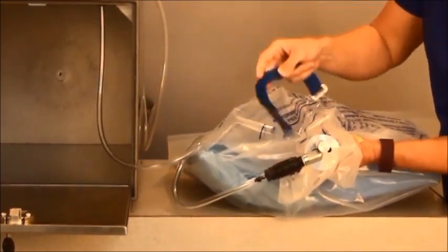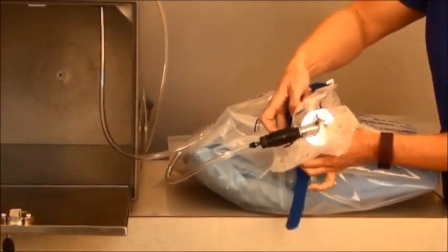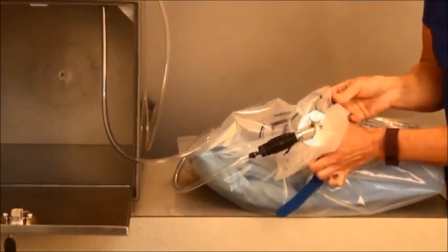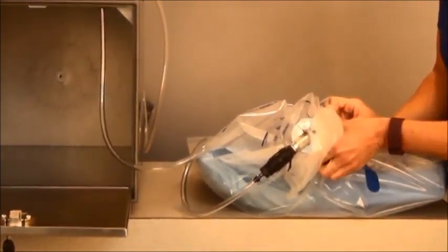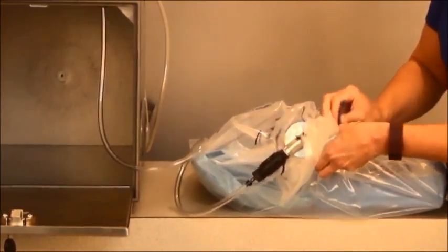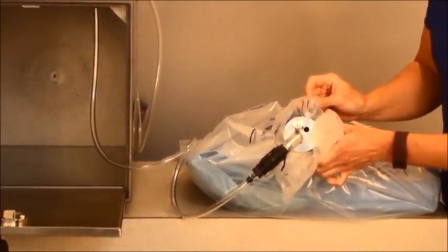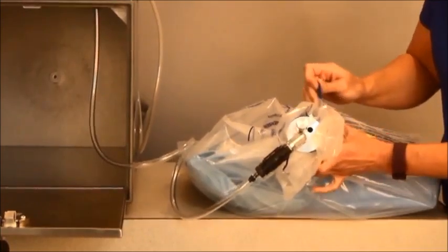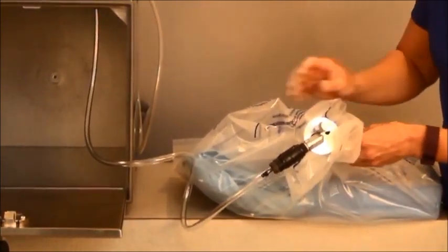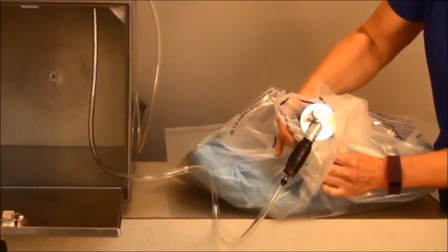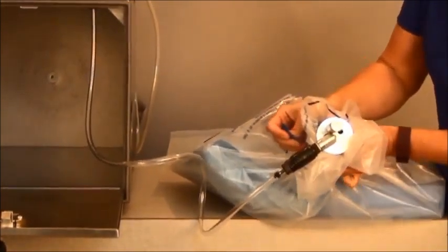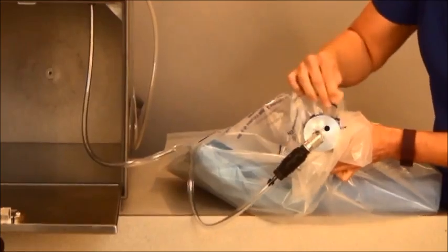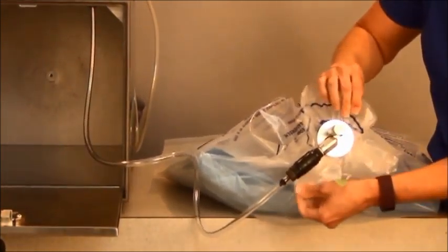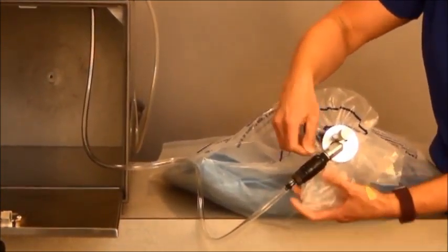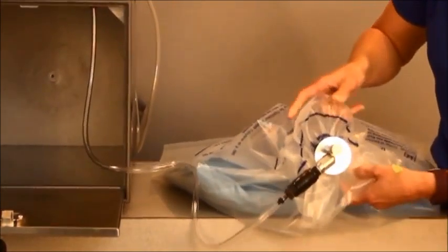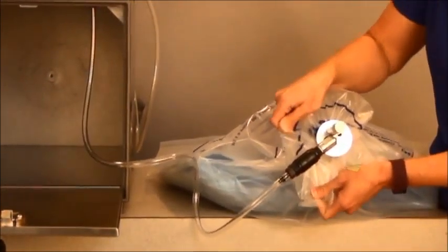When running cycles, you always want to use this point of reference so all of your cycles are the same and uniform. Pull the Velcro strap as tightly as you can around that silver bobbin. And then spread out the gathered part of the sterilization liner bag around the bobbin to make sure that you don't have any gaps.